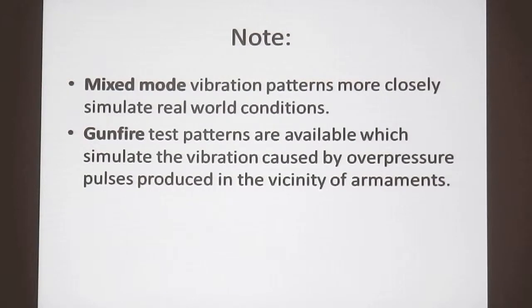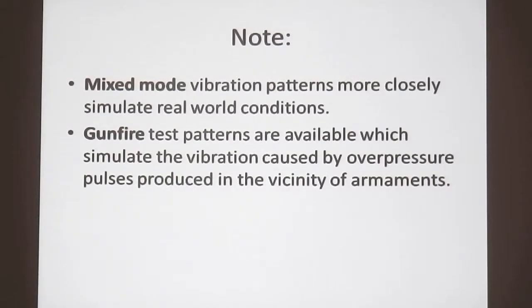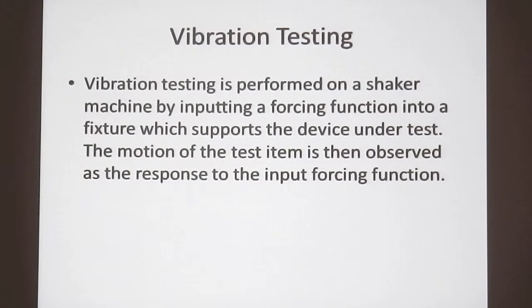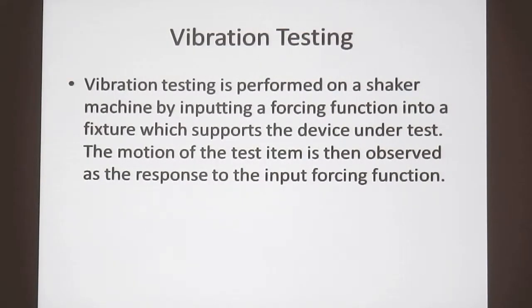We also have the ability to simulate gunfire test patterns, and they are available in service mode, which simulate the vibration caused by over-pressure pulses produced in the vicinity of armaments. Vibration testing is performed on a shaker machine by inputting a forcing function into a fixture which supports the device under test. The response or motion of the test item is observed, and that is the response to the input forcing function.